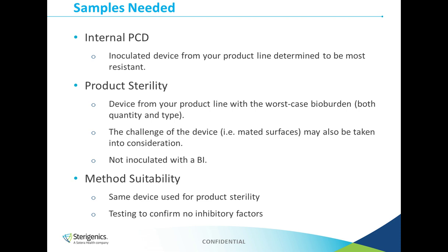In other words, if you have 2 devices with the same amount of bioburden and one is a surface sterilization device and one has more complex design, such as tubing or a syringe, you're going to choose that tubing or the syringe because it has more of a challenge for the EO gas to get to that bioburden and get the kill. Now remember that the product sterility samples are not inoculated with a BI or any liquid inoculum. It's just that natural product bioburden that's on the device.